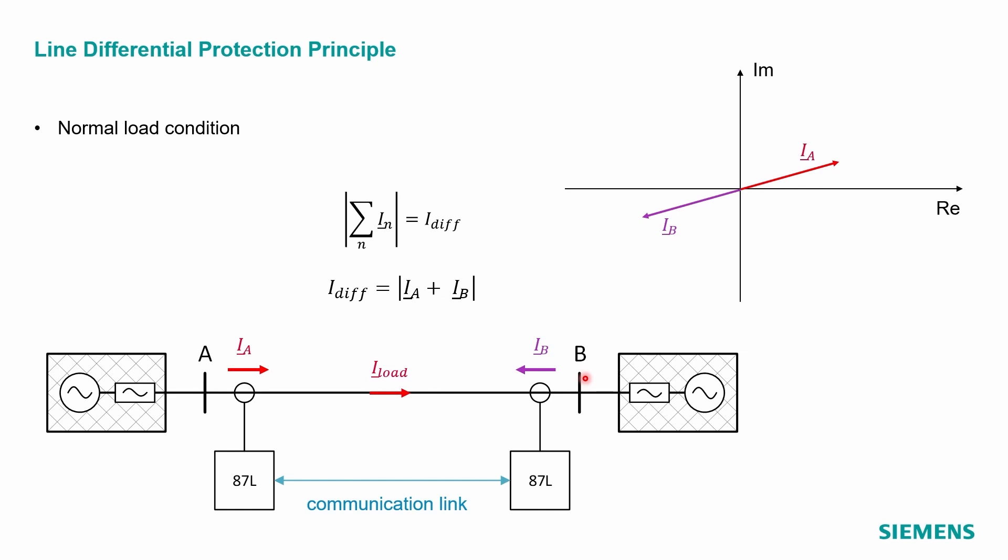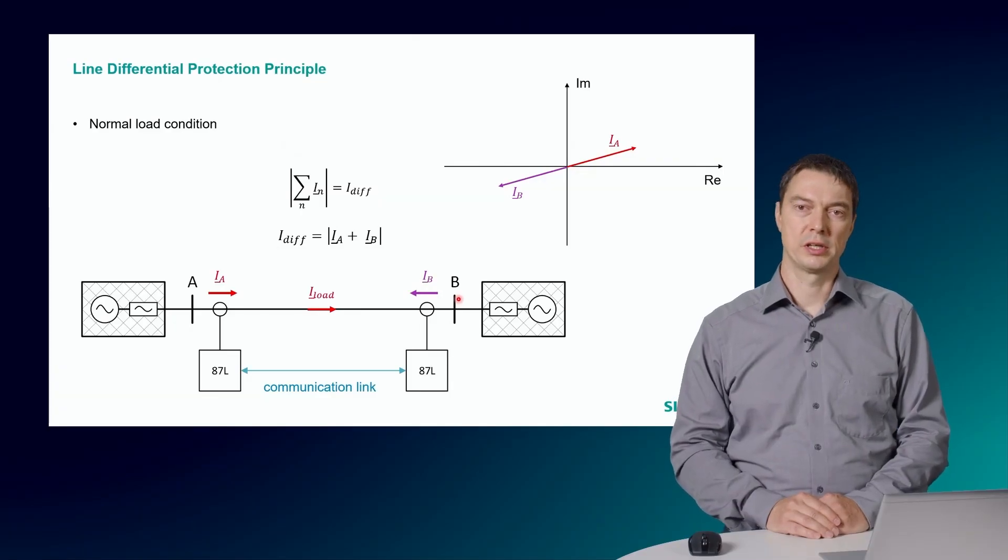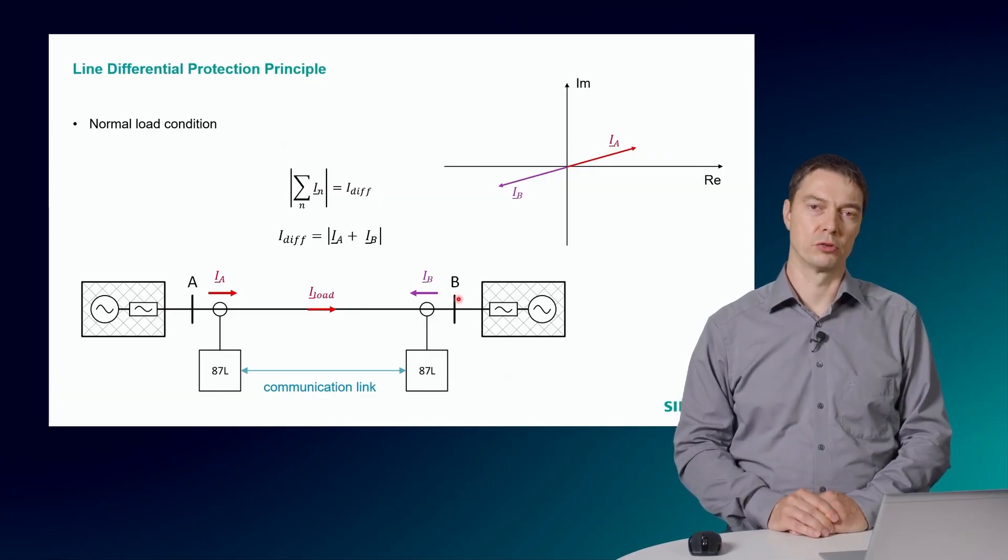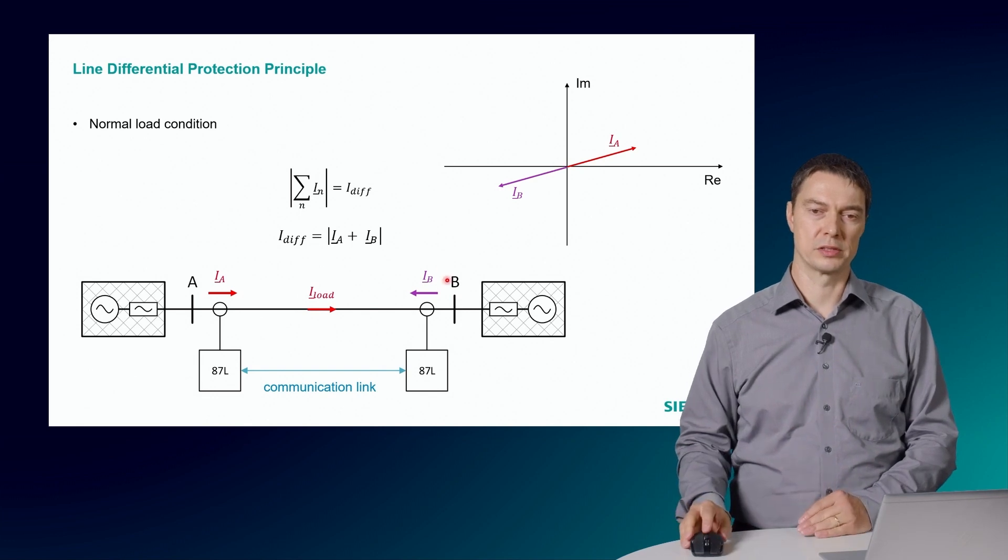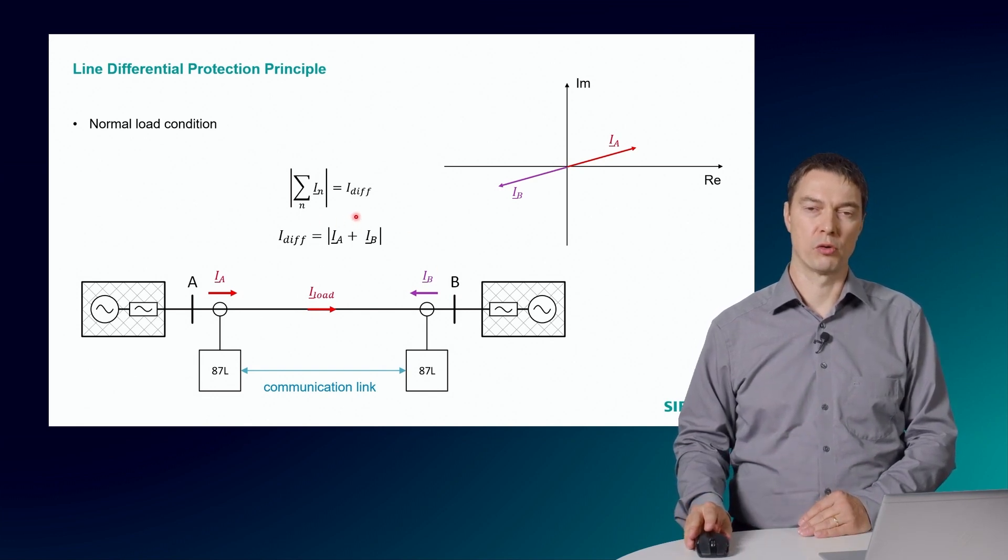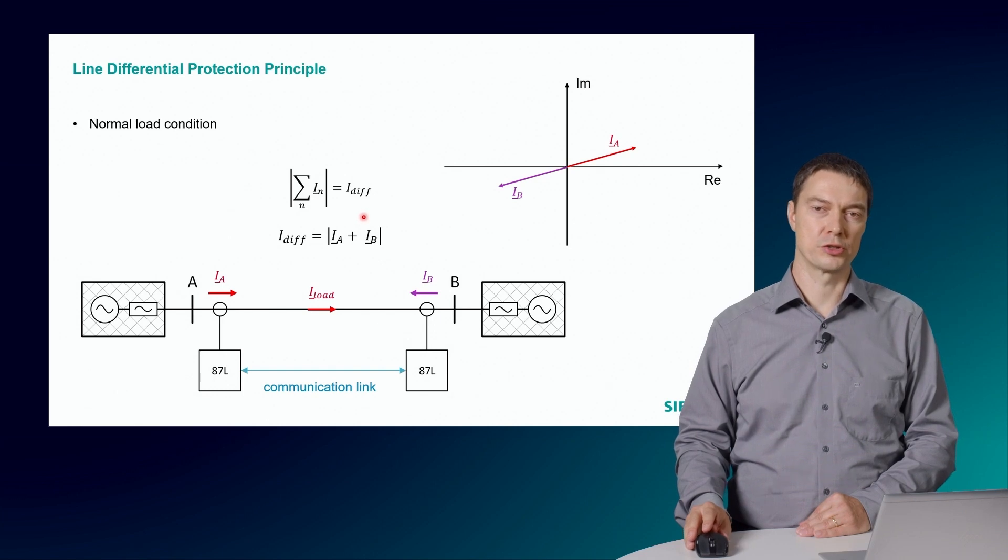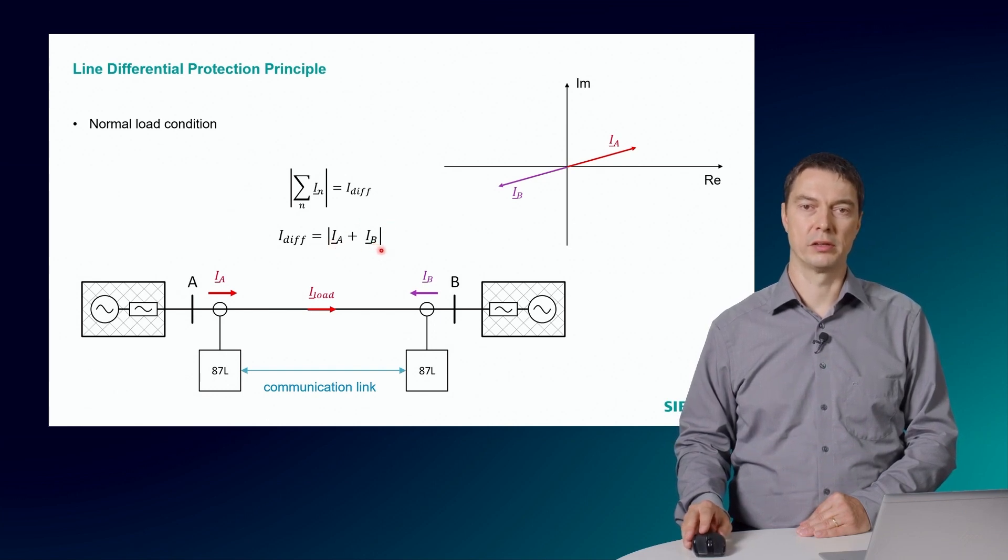The current phasor is therefore in the opposite direction. Most relays in the market will calculate the differential current as the sum of the current phasors from N terminals. For our two ended application, the differential current is therefore IA plus IB and then the absolute value.